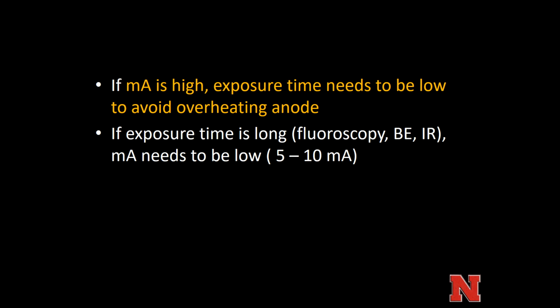So oftentimes when things are set up, it will be a direct kind of opposite effect of mA and exposure time. If you have a setup where your exposure time can be very low, like it's on for a millisecond taking a single wrist radiograph, you can have your mA relatively high. But what if you're in fluoroscopy doing an enema study that takes a half hour, or an IR procedure where the fluoro is going to be on for a couple of minutes or maybe even an hour, doing a complex IR procedure?